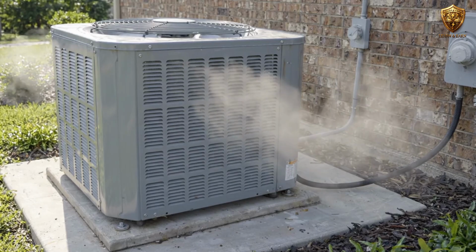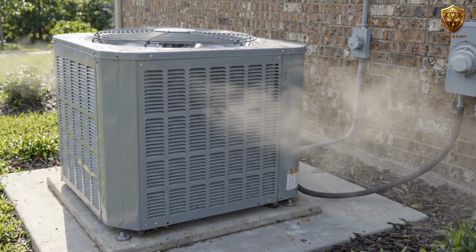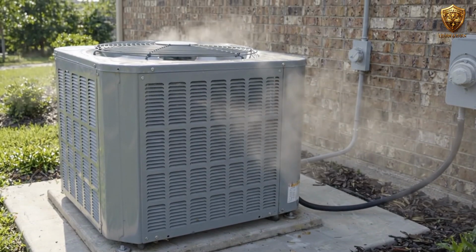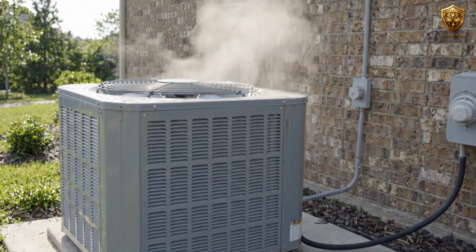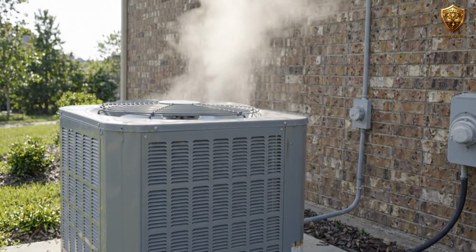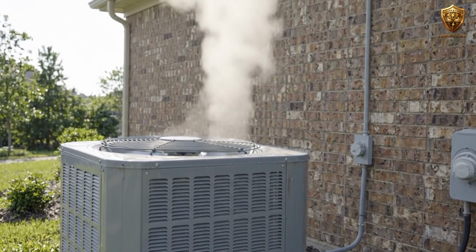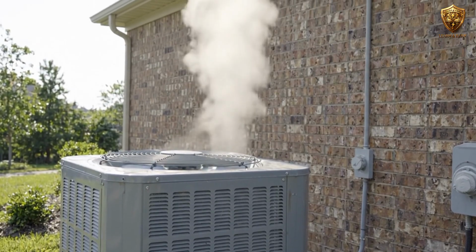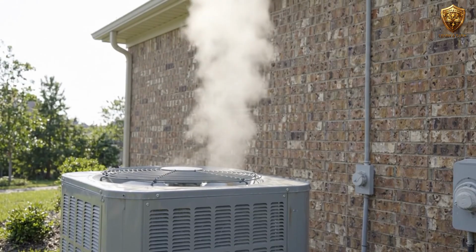The technician should first determine whether the motor is receiving the correct power and control signal and then test the motor and capacitor according to the equipment design. The physical condition of the condenser coil also matters. Cleaning should be done using a method appropriate for the equipment and coil material. Excessive pressure can damage delicate fins, so aggressive cleaning is not automatically better.